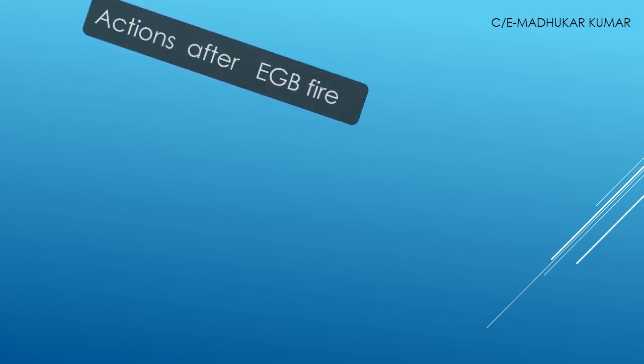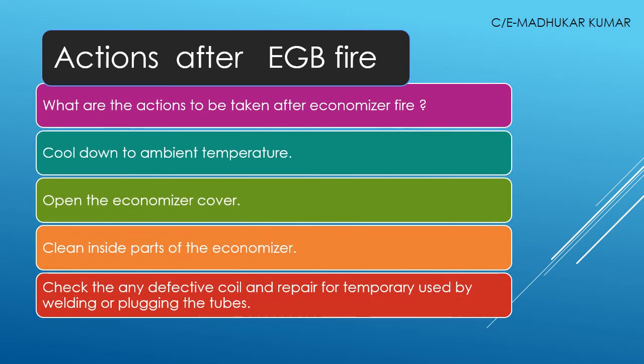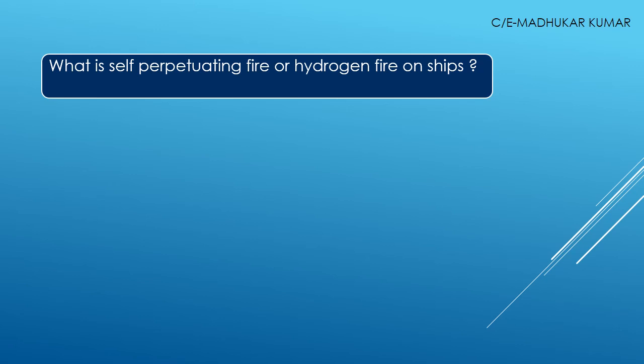Actions taken after the EGB fire: Cool down to ambient temperature, open the economizer cover once it is cooled down sufficiently, and clean the inside parts of the economizer. Inspect and identify defective coils, tubes, and pipelines. Make sure these can be repaired — welding of tubes or plugging of tubes may be necessary to ensure no water leakages, and the EGB should be returned to a stable condition.